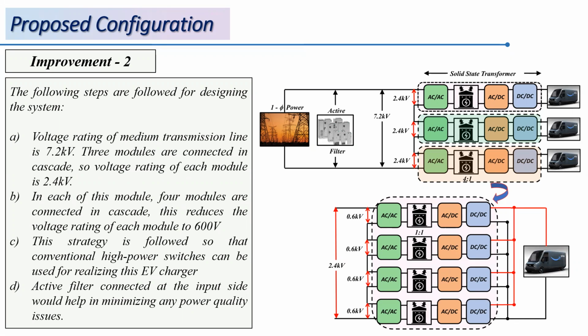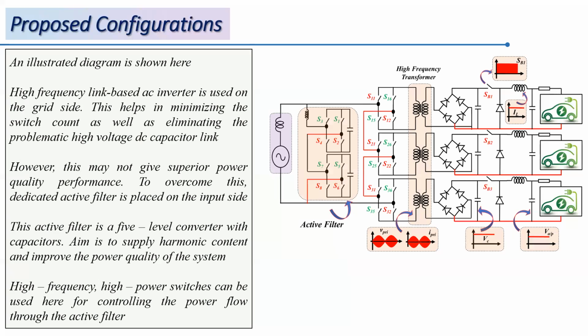An illustration of the proposed circuit is shown on the right. As you can see, we are connecting the charging station to one of the phases of a 7.2 kV line to line voltage. Each module consists of four sub modules connected in parallel, so that the power rating at the output can be increased. So if you see now, the switch rating required in each module is reduced to 600 volts, so we can use conventional power rated switches, which have a very good and mature technology, right?